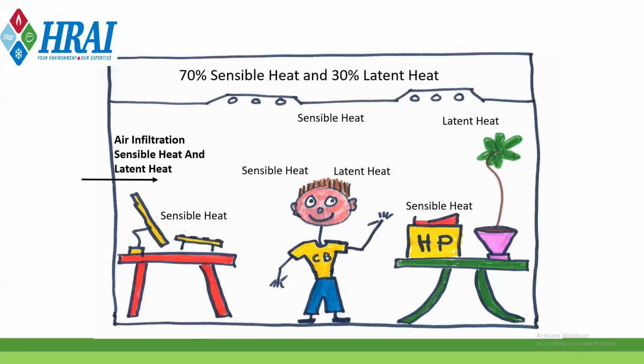Now, the sensible load, as you all are aware, is what raises the thermostat up and down. It comes from infiltration, like latent as well, with people, computers, and other things in a space that emit heat. So most systems today are designed to handle both sensible and latent loads in one piece of equipment, whether it's the air handling unit, the fan coil unit, package unit, etc. Now, with the chilled beam systems, we physically want to decouple the latent load and the sensible load. This is the core design principle that drives tremendous operating savings within an active chilled beam system. So the latent load in this example would be handled with a dedicated outdoor air system, or DOAS for short, and the sensible load is handled in the space by the active chilled beam.